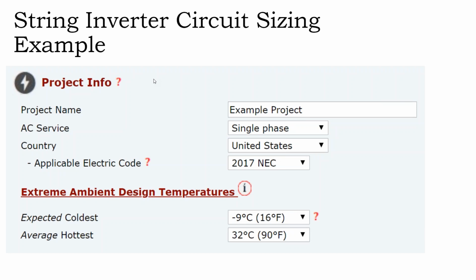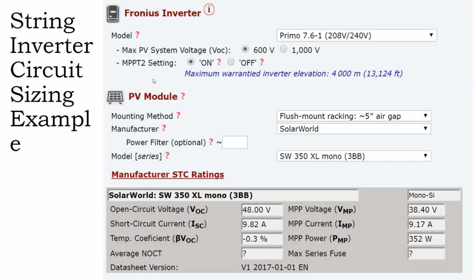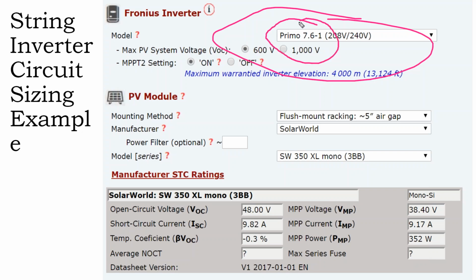Okay, so in a regular string sizing software, you're inputting your temperature conditions and you're inputting what inverter you're using. And so, if we go and buy 10 kilowatts worth, one pallet of solar, we could select, this is a 25% undersized inverter. We could buy a 7.6 kilowatt inverter. We could also buy a 10 kilowatt inverter. Personally, nowadays, I wouldn't undersize by 25%. I'd just go spend a couple $100 more on the next size up.